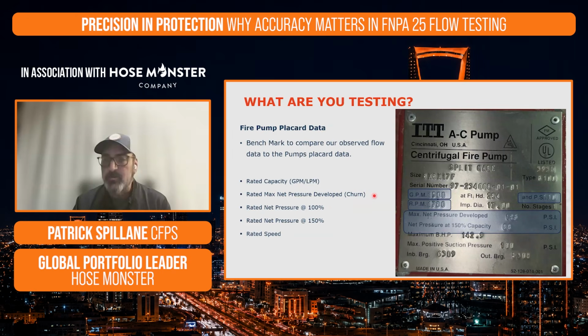That's going to be our churn pressure when the fire pump is not flowing any water. And then we also have our two net pressure readings while that fire pump is flowing 100% of its capacity and 150% of its capacity. So again, this 1,500 gallon per minute fire pump will have a net pressure, which we'll talk about here in the next few slides. Net pressure is the pressure developed by that fire pump. That's the discharge pressure minus the suction pressure equals your net pressure.